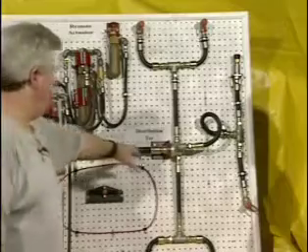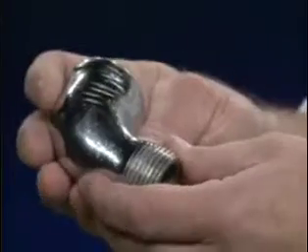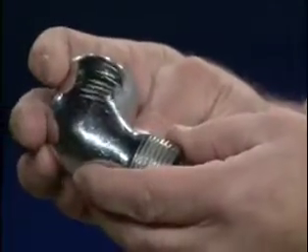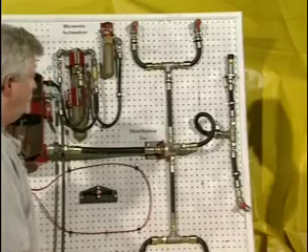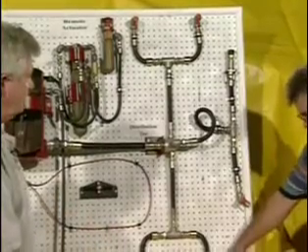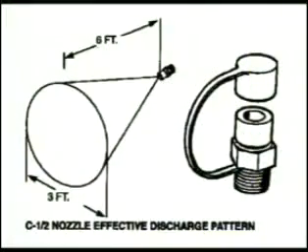From the tank to your distribution T, which we have here, because this is a 6-nozzle system. I understand that this street L cannot be used because it isn't listed or approved in any of the distribution systems. From this point on, everything is 1/2-inch. Got different nozzles on the Ansul system. You can notice them down here, Don. The bottom one's down here. That's a C nozzle. And what kind of pattern does it get? That throws out a cone pattern. It'll throw out a pattern 6 feet out and open up to a diameter of 36 inches.